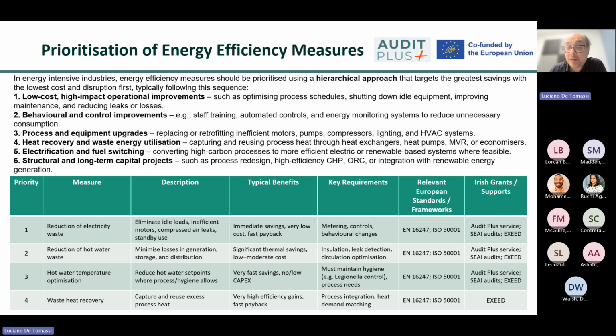Such investments typically require moderate capital expenditure but can deliver substantial and sustained reduction in energy consumption. After minimizing energy demand, attention should shift towards recovering and reusing energy that would otherwise be lost from industrial processes. Examples include waste heat recovery from process exhaust streams, cooling systems, refrigeration systems, or wastewater, installation of heat exchangers and economizers to capture and reuse thermal energy, mechanical vapor recompression systems for evaporation and concentration processes, integration of recovered heat into hot water generation or process heating applications. Heat recovery measures can significantly reduce fuel consumption by displacing primary energy requirements with recovered energy.